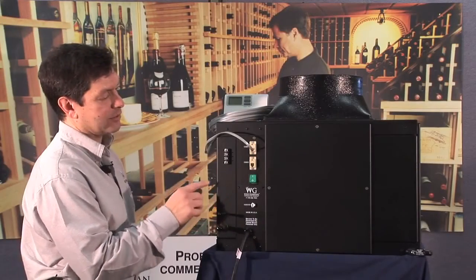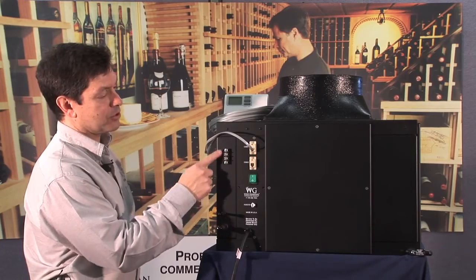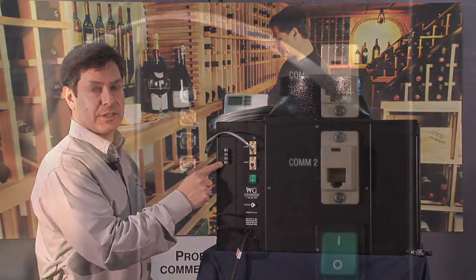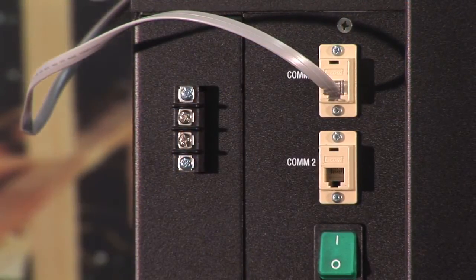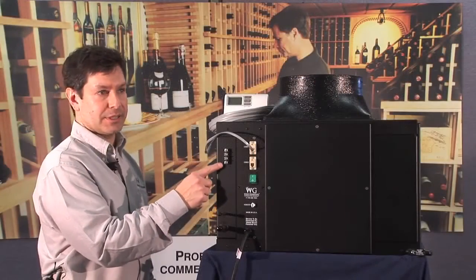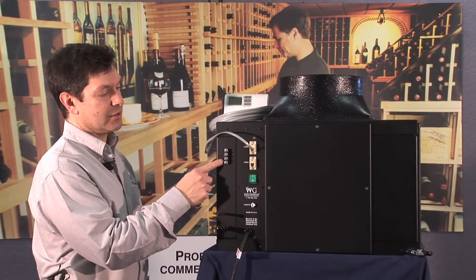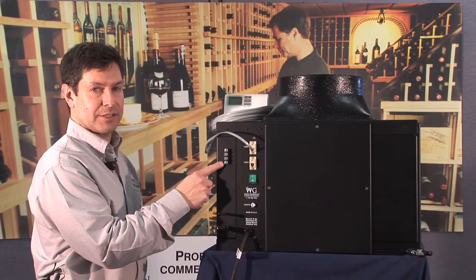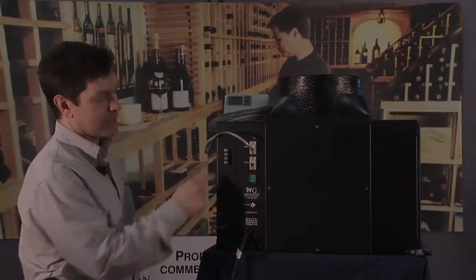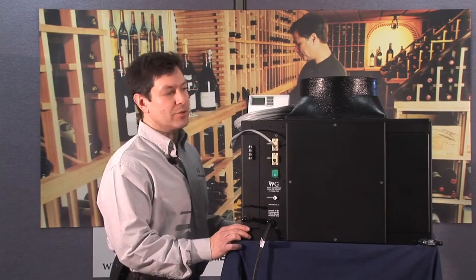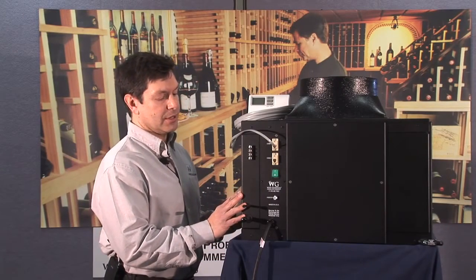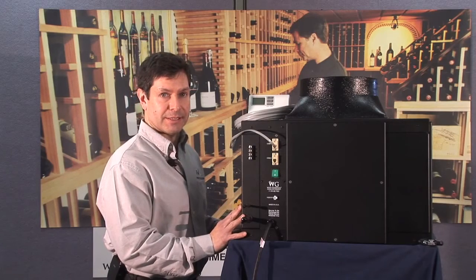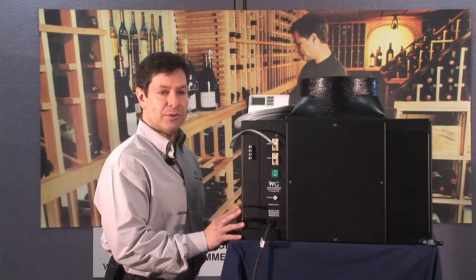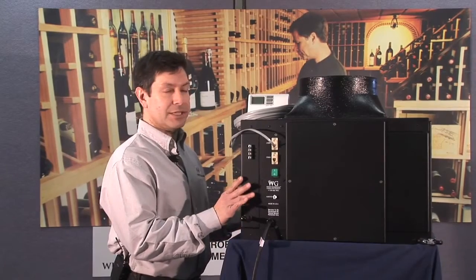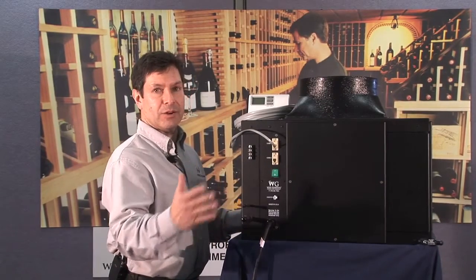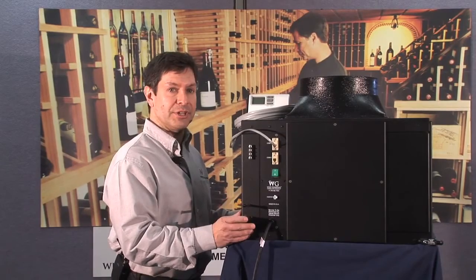Along with our main control panel, you'll see a terminal strip here. This is 24 volt control wire from the fan coil section out to the condensing unit. This is a key feature, and your installer will be looking for this to make connections when they're doing the installation. Similar to our self-contained ducted units, our fan coil sections include high static pressure fans. This gives you the ability to connect ductwork up to these sections and extend that over to the wine cellar, both supply and return.